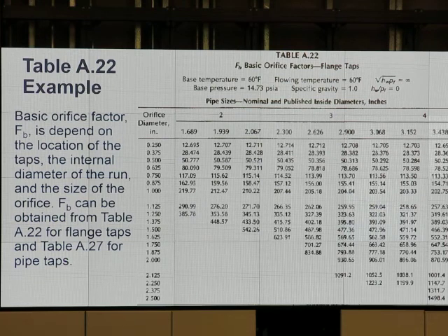the accuracy goal is acceptable if the pressure drop across the orifice plate is somewhat less compared to the static pressure. So let's say if I have static pressure of just 20 psi A, okay? Static pressure of 20 psi A. And I have the pressure drop across the orifice, another 20 psi A. It's not good. The reading doesn't work. Okay? HW over P sub F will be equal to 1.